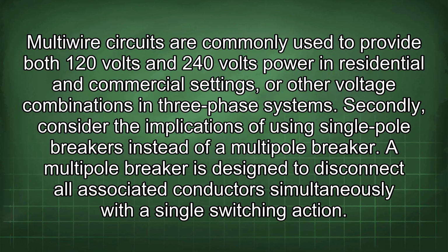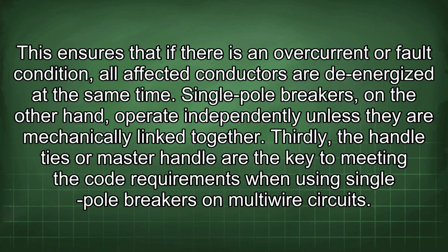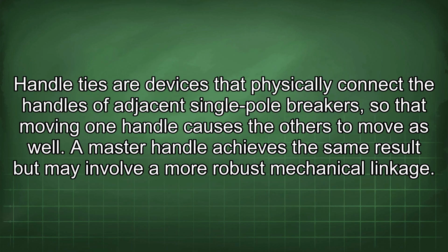Secondly, consider the implications of using single-pole breakers instead of a multi-pole breaker. A multi-pole breaker is designed to disconnect all associated conductors simultaneously with a single switching action. This ensures that if there is an overcurrent or fault condition, all affected conductors are de-energized at the same time. Single-pole breakers, on the other hand, operate independently unless they are mechanically linked together. Thirdly, the handle ties or master handle are the key to meeting the code requirements when using single-pole breakers on multi-wire circuits. Handle ties are devices that physically connect the handles of adjacent single-pole breakers so that moving one handle causes the others to move as well. A master handle achieves the same result but may involve a more robust mechanical linkage.